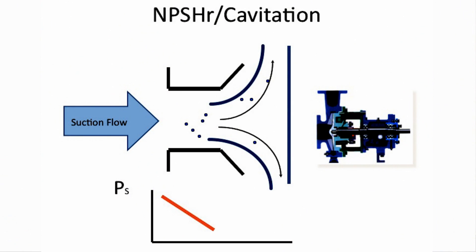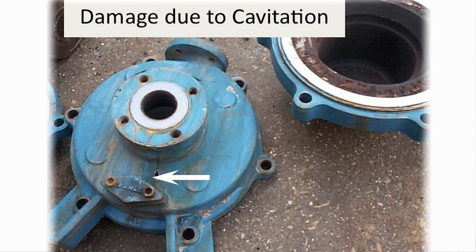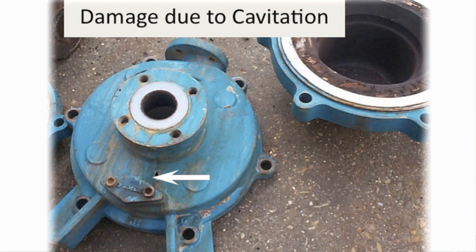The sketch shows the flow of liquid as it enters the pump. The pressure drops until it meets the eye of the impeller. If it hits the vapor pressure, vapor bubbles form, and then as they leave the pump, they collapse. The picture shows damage to a lined pump handling acid — cavitation caused a failure in the lining and the acid ate right through the pump casing.